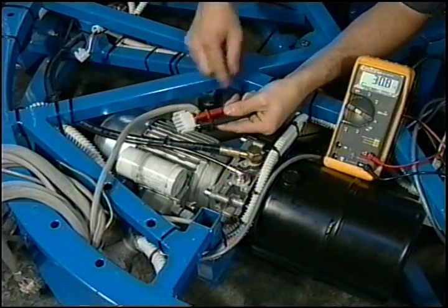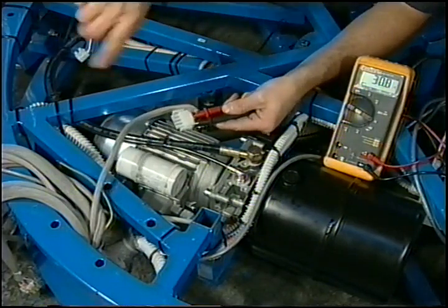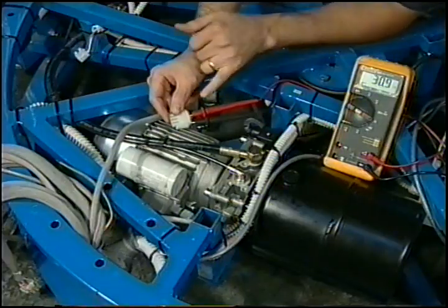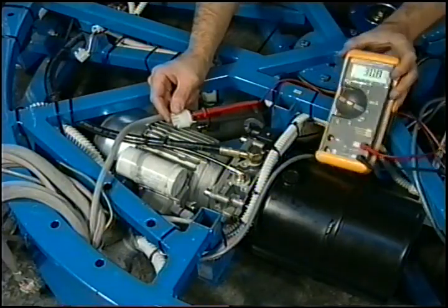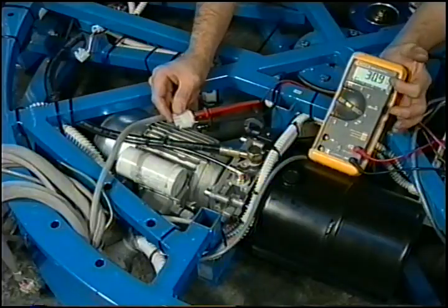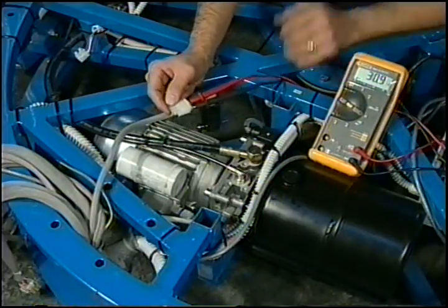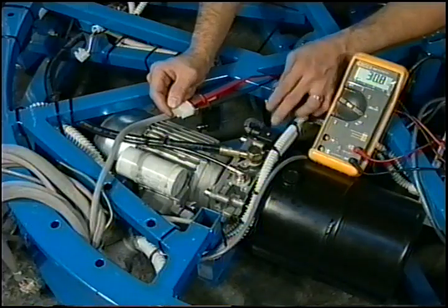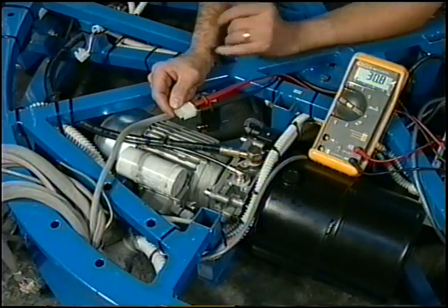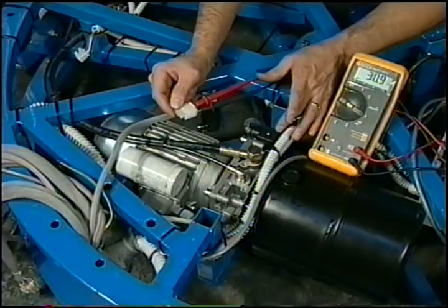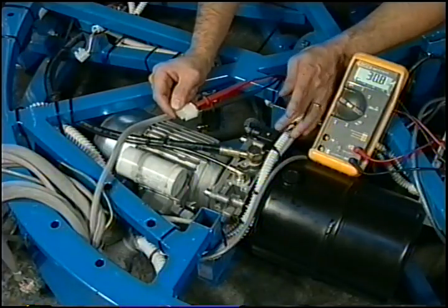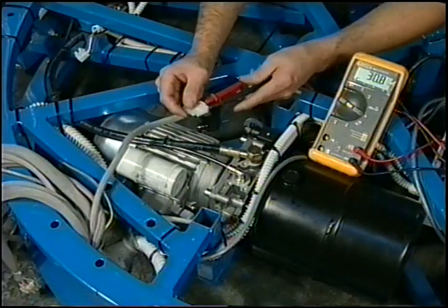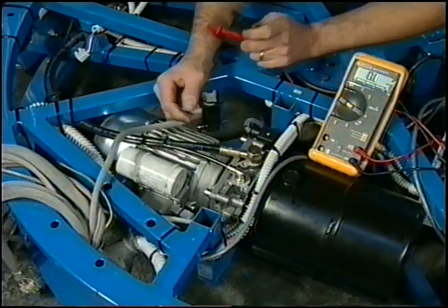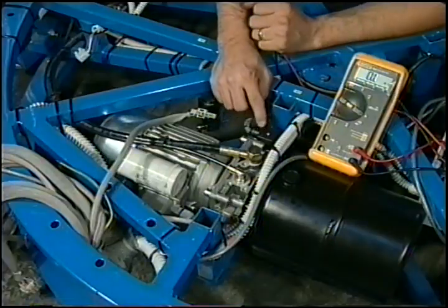The 2 yellow wires are going to your home switch for your rotation, so we're not going to concern ourselves with that now. When we read across that, you're going to read anywhere from 30 to 40 ohms. And that's reading directly. So when you're doing that, you're checking both your wiring from the CPU board to your coil, and you're also testing the coil itself. Now that's just the coil.